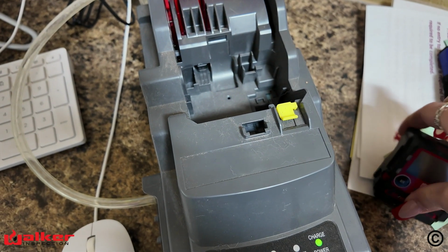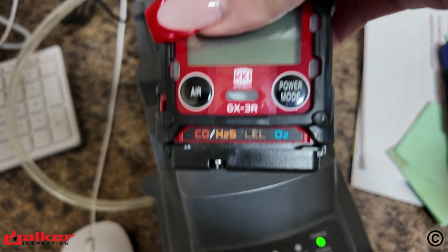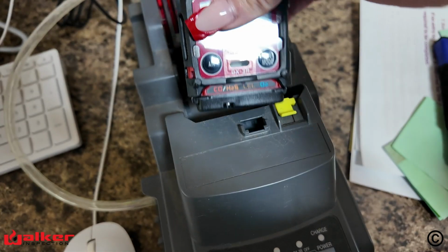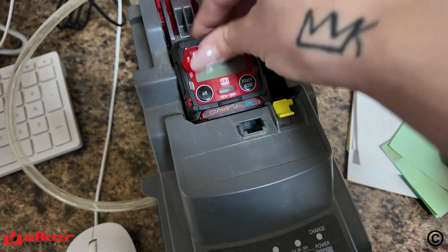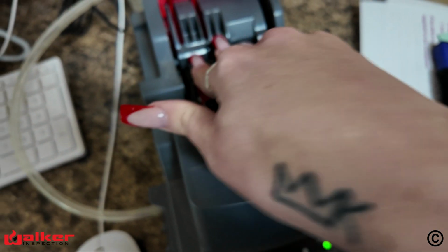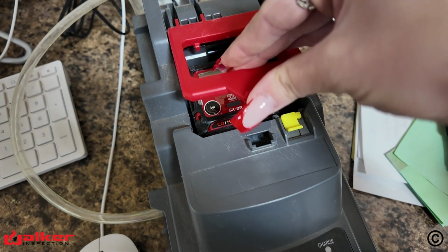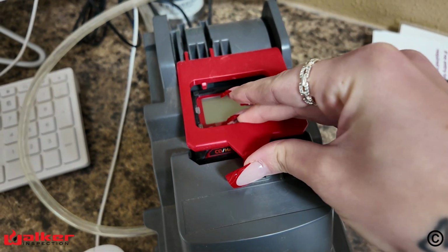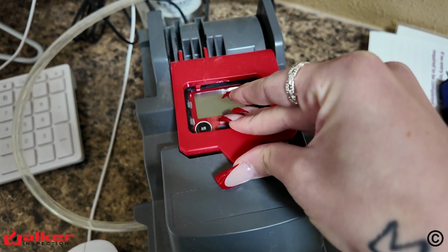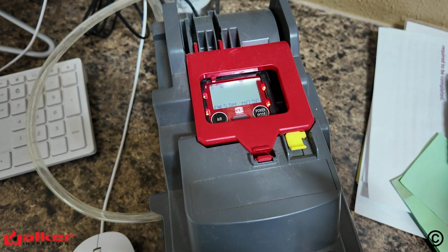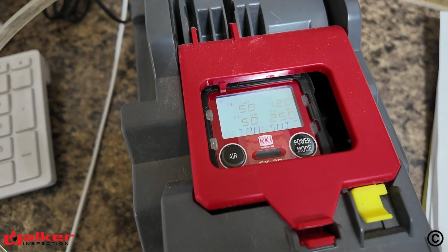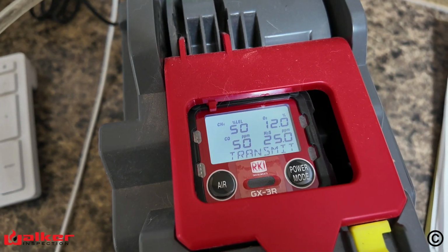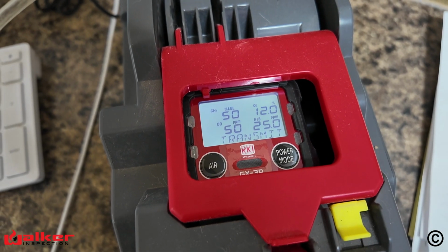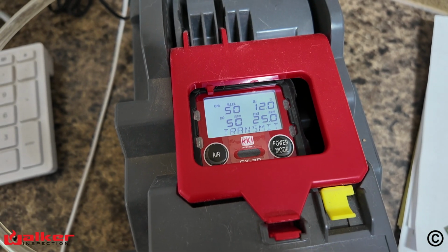The monitor needs to be off first. To place the monitor in the docking station, place it in bottom side first where the gas filters are, then push the top side down and it will click once fully connected. The red bracket will come down over the monitor. This bracket can get stuck and may need to be moved slightly to open. However, be very careful as it is plastic and can break easily if too much force is applied to it. The bracket must lock in or you will not be able to perform the test.